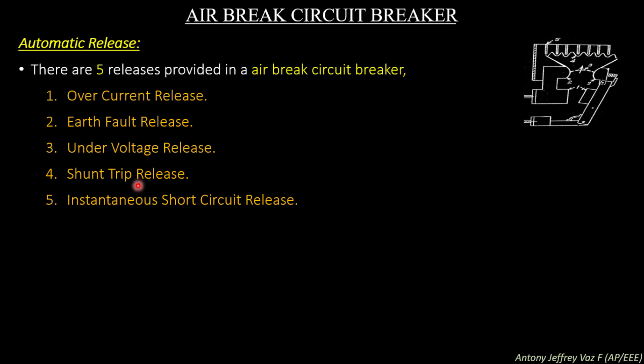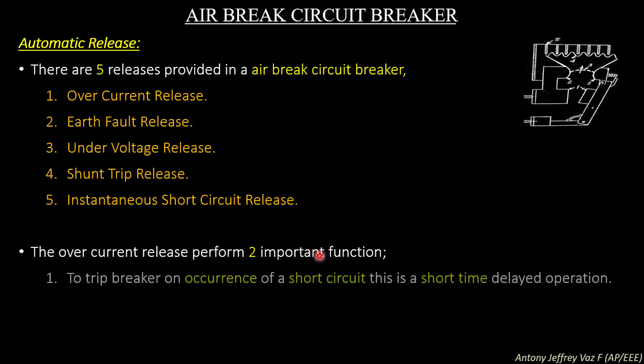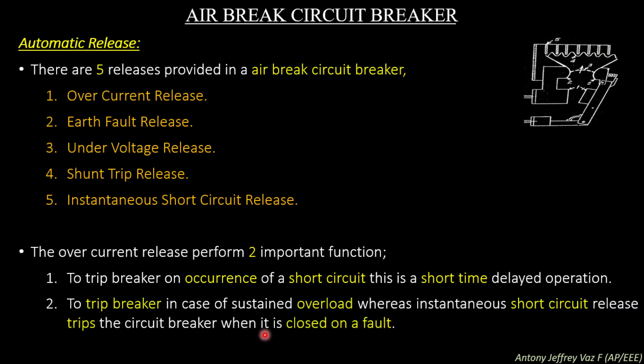These five protections are present inside the air break circuit breaker. The over-current release performs two main important functions: to trip the breaker on occurrence of a short circuit in a short time delayed operation, and to trip the breaker in case of a sustained overload. The instantaneous short circuit release trips the circuit breaker when it is closed on a fault. Overloading occurs when more current passes through the contacts than the circuit breaker's rating, and this percentage increase also trips the circuit breaker contacts due to over-current release.